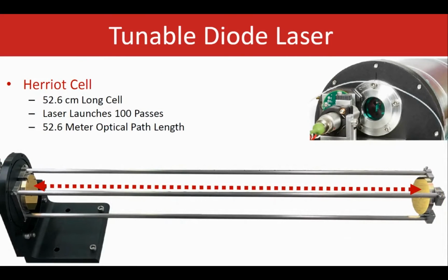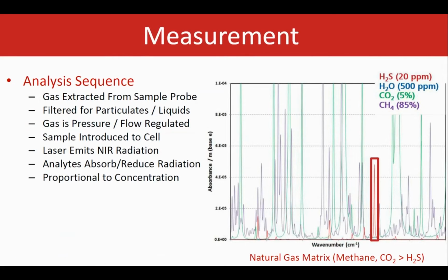Now this is another view of the cell, which shows where the mirrors are located. You see clearly at both ends of this cell is where the mirrors are. So it's a simple and robust design to work with. Now for the analysis side, the gas is extracted by the sample probe. The gas gets filtered in case there are any particulates, any liquids, anything like that in the stream, so we get rid of that. And the pressure gets regulated.